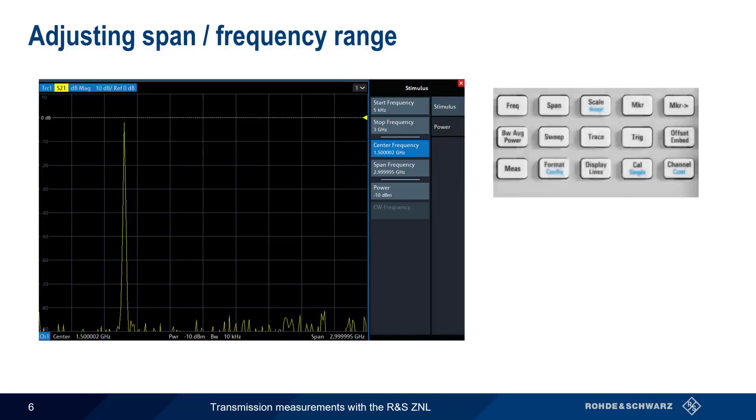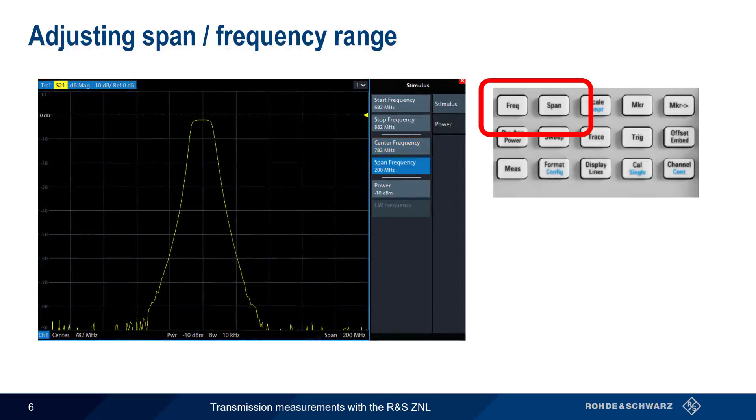After selecting S21 or S12, the results are automatically displayed on the ZNL screen. If the displayed frequency range or span needs to be adjusted, use the Frequency and Span hard keys and associated soft keys to adjust the center and span, such that the trace is easier to read and work with.